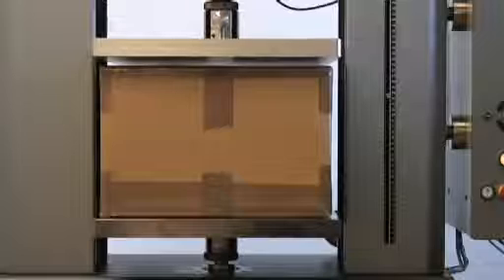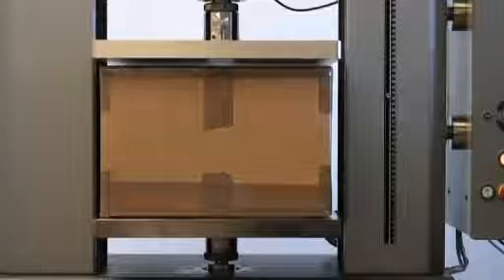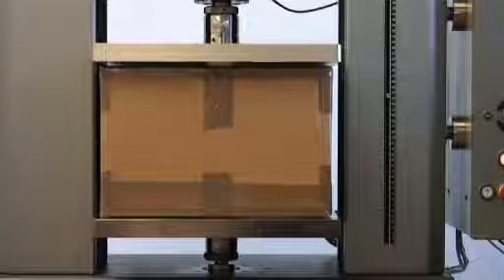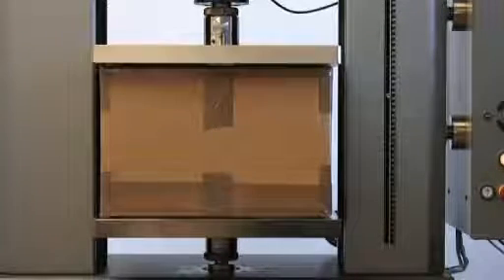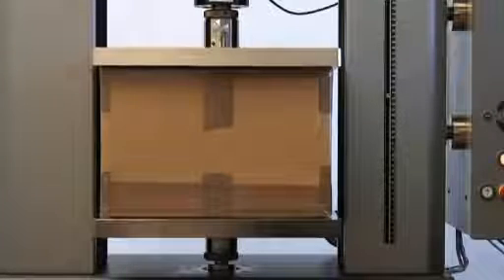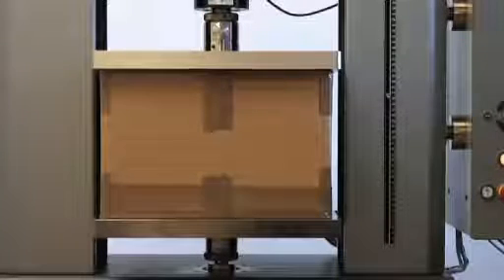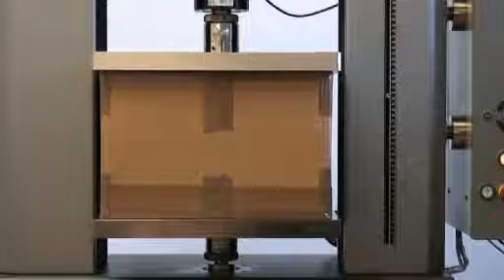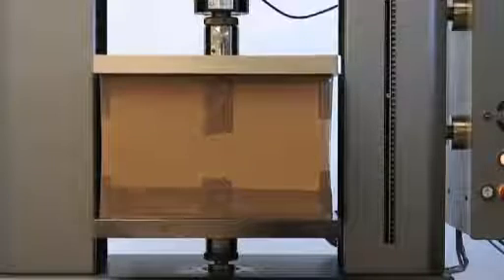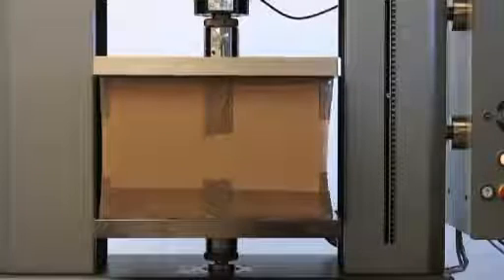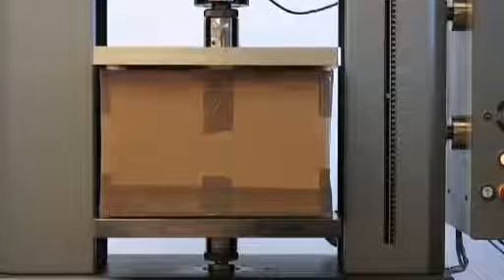The upper platen is lowered towards the lower platen to measure the force required to crush, in this case, a box. The force reading given to crush or deform a box can also be calculated back to understand the stacking factor or the weight a container can withstand.